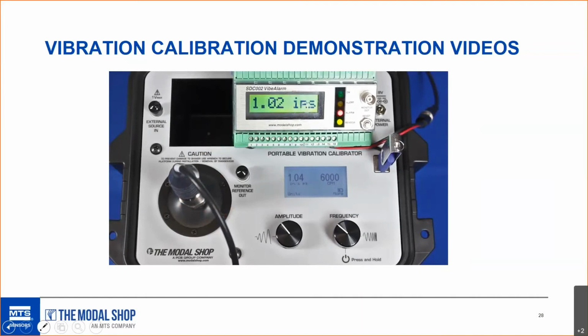Yeah, and you see a slight difference there. The vibe alarm is anticipating a 100 millivolt per G transducer, and perhaps the output of that transducer was 99.5 or whatever it works out to be. And that'll be the case with anything you test.